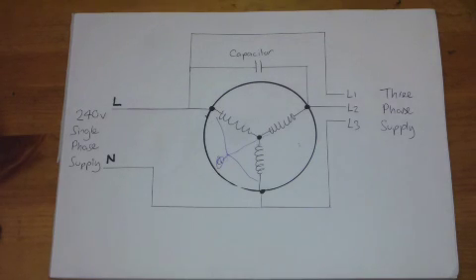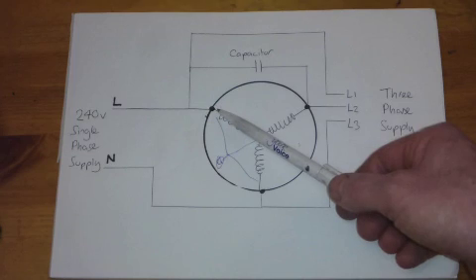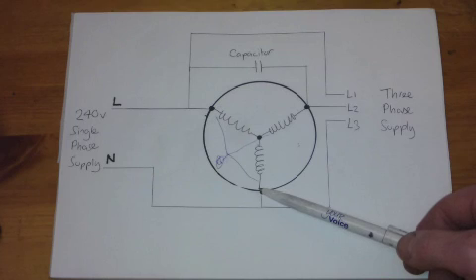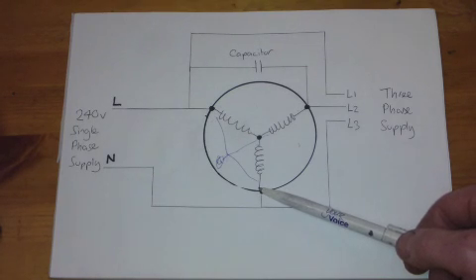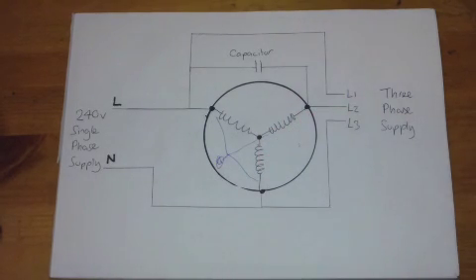It does work however if your machines don't need neutral loads of people it'll do fine. If you look between any two of the phases there's one phase there and there's another phase there that should be 415 volts shouldn't it? If we look back where it's coming from it's only 240 volts. So this arrangement here requires you to have dual voltage motors which you can dive into alter the connections and make them run from 240 supply.